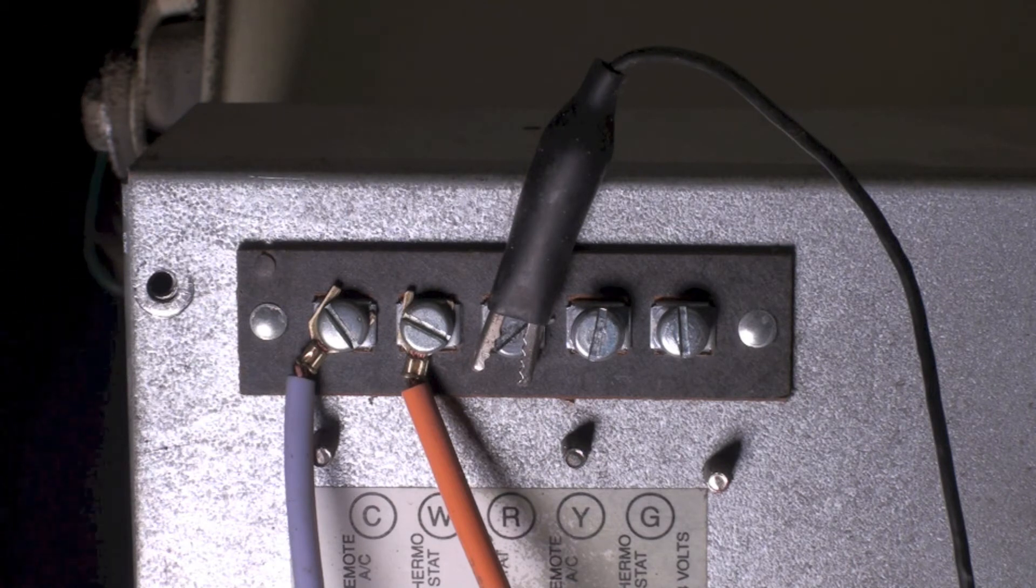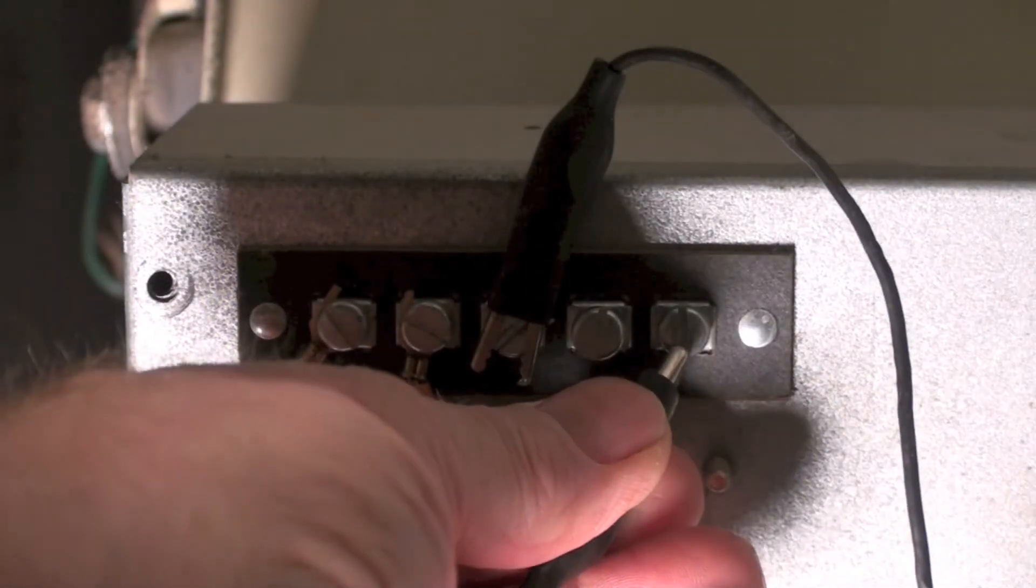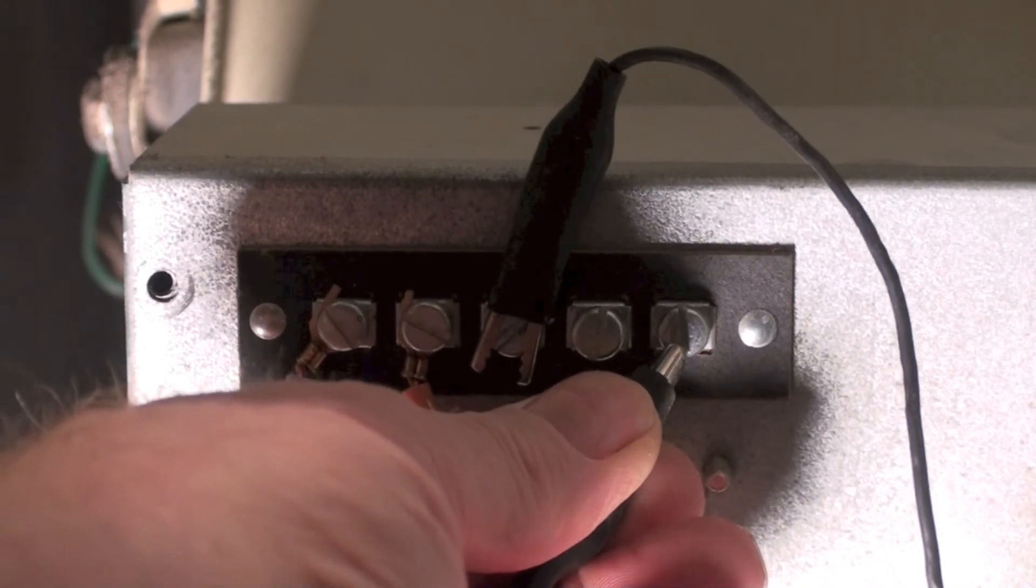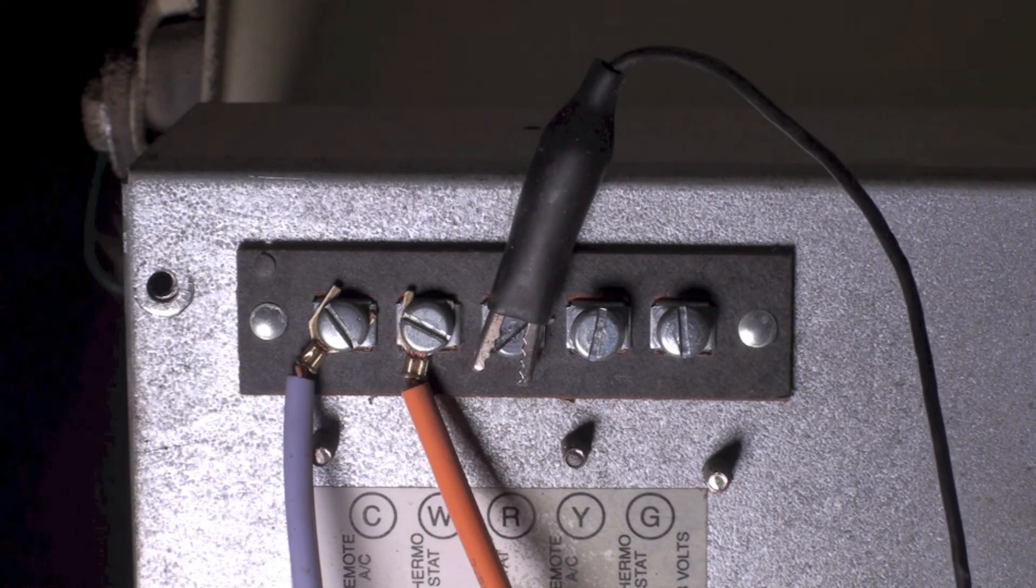In order to find out if there's power to the unit, there's a real simple way to do it. You just jumper right there. The fan came on - it went from R to G. Now you know you've got power.